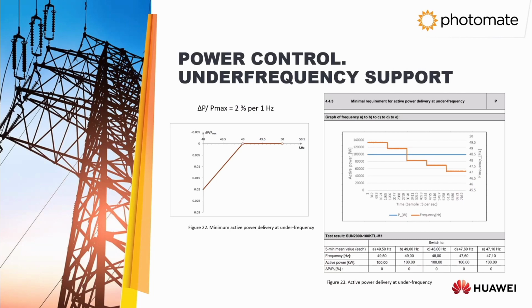A very common request from DSOs, in the requirements for generators, is that a generator cannot decrease its power when the frequency is decreasing by more than 2% per 1 hertz of drop. It is a very good advantage of solar inverters that they do not decrease the output power according to the frequency at all. So it can work at 100% even at lower frequencies, as shown in figure 23.